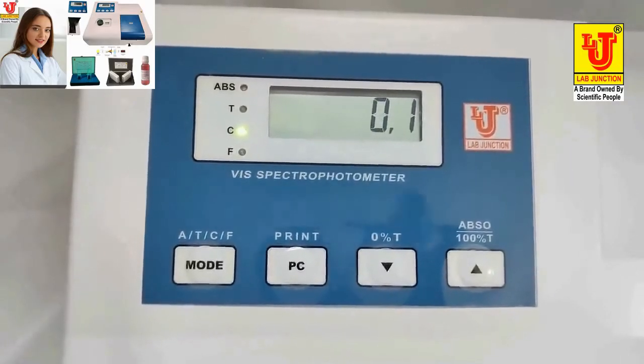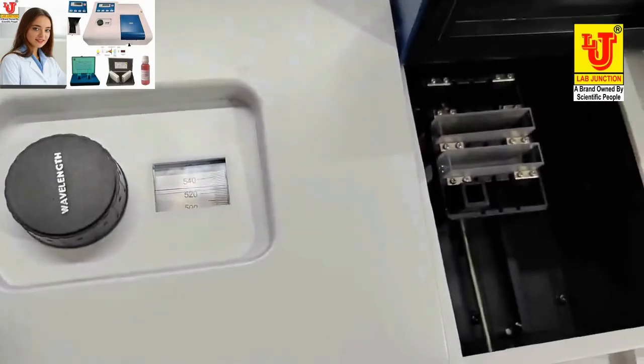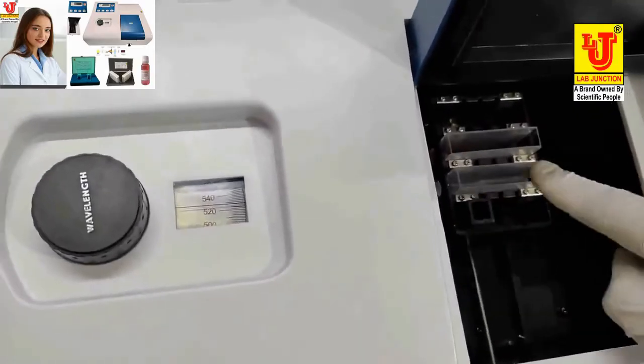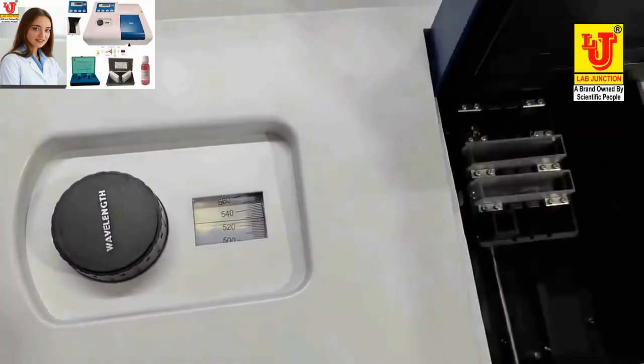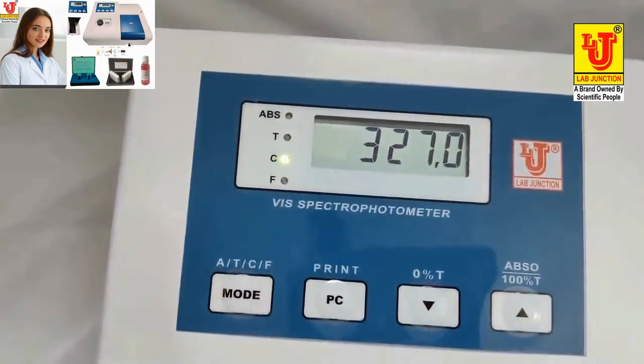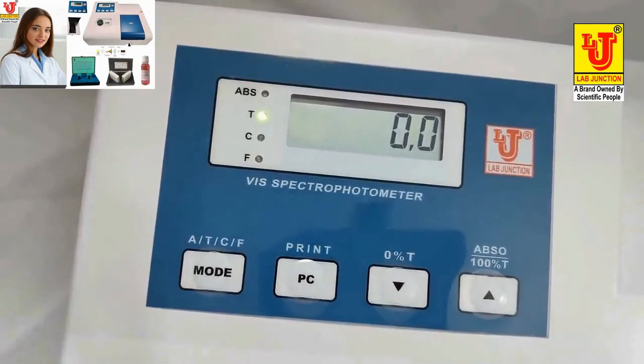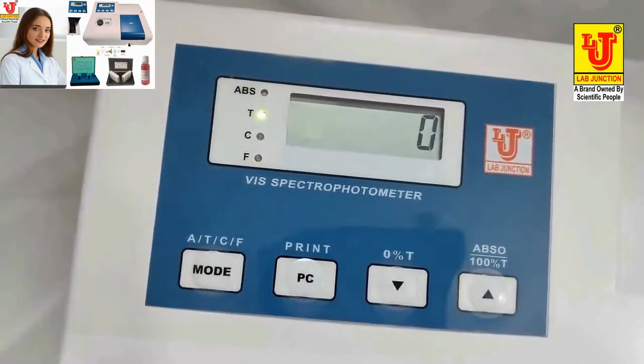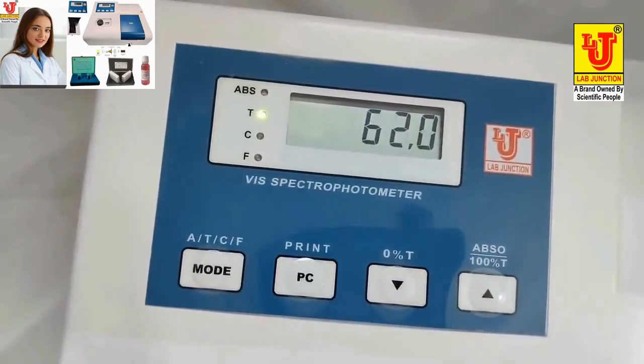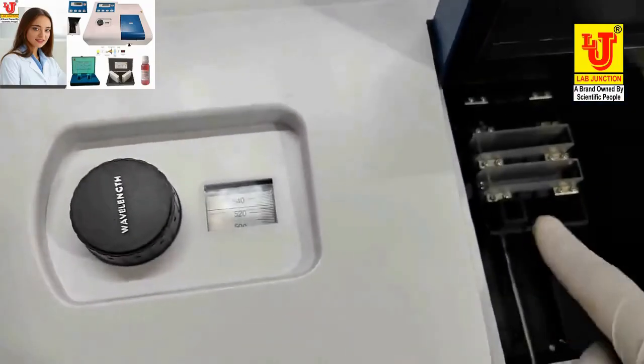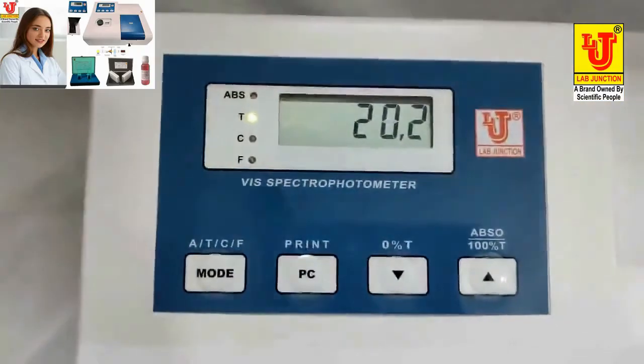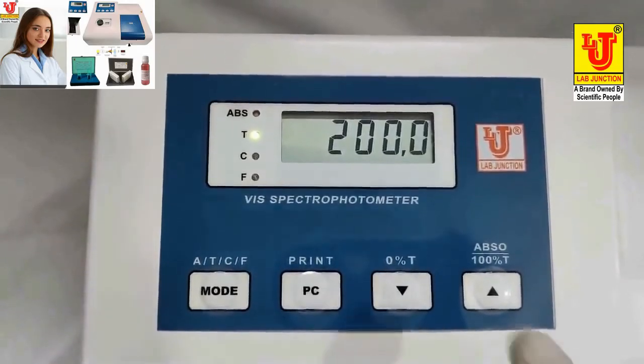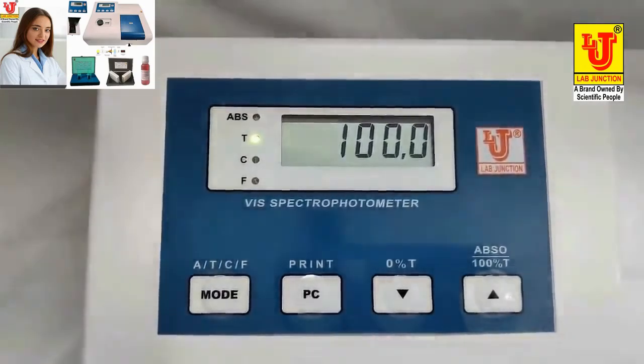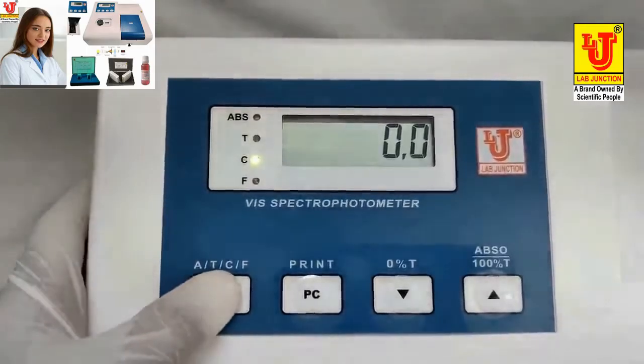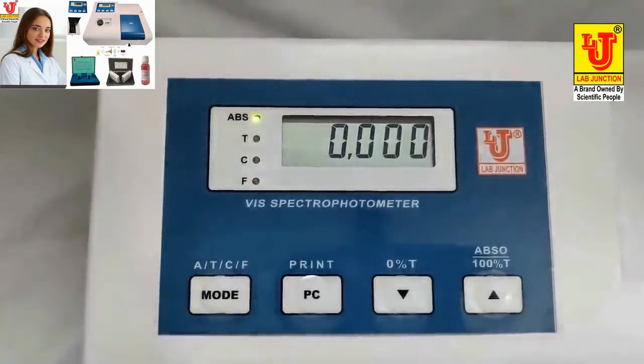Again I am describing. This is the dummy. First position blank, second position sample. Now first go to transmission mode. Press 0% T for preset 0. Now press 100% transmission. This is not working. Why? I am not placing this. See, this is on the dummy side. So when I go to transmission this way, now pressing 100. Now 100% transmission is there. Now I am going to absorbance mode. Absorbance is 0. If transmission is 100, absorbance is 0.